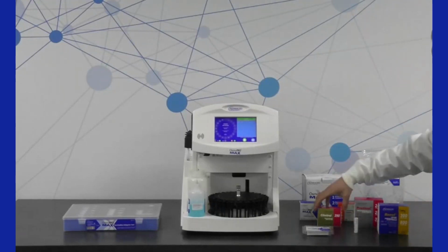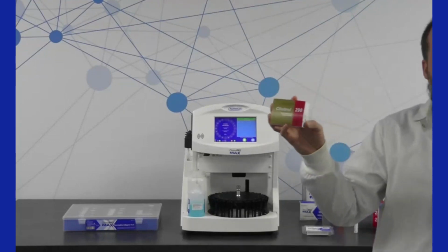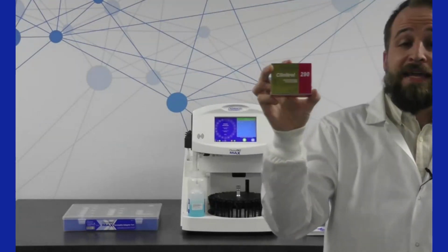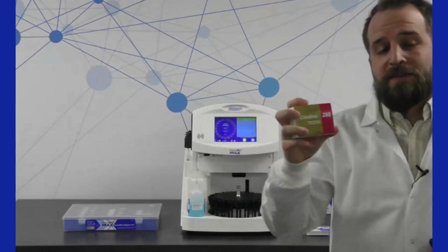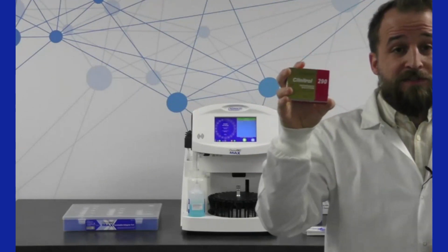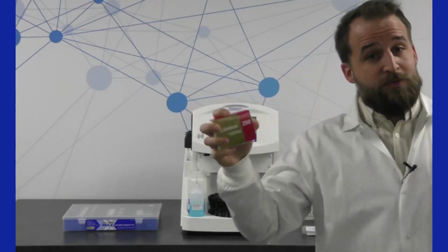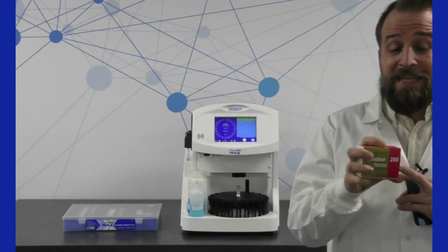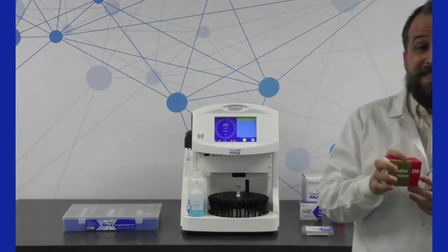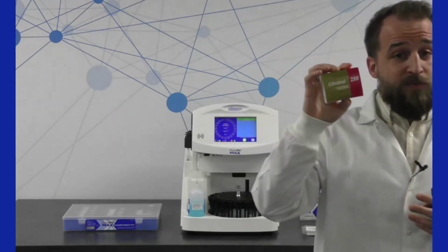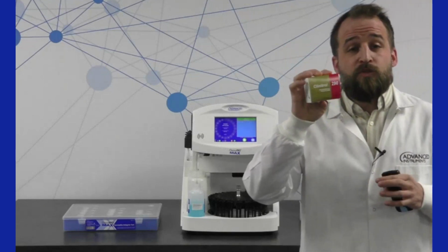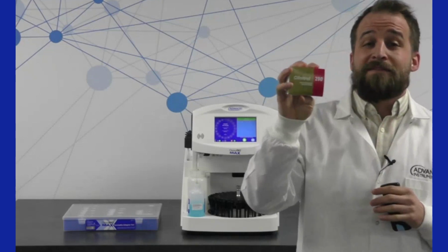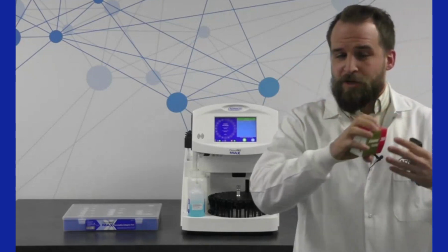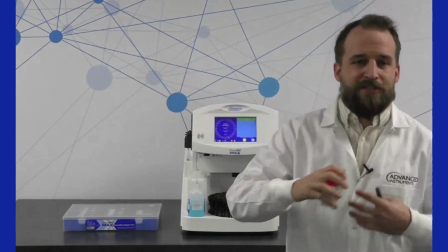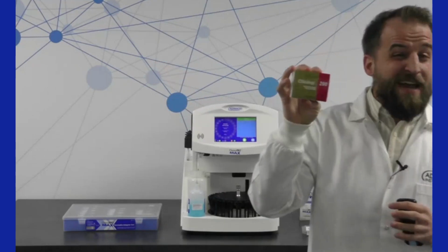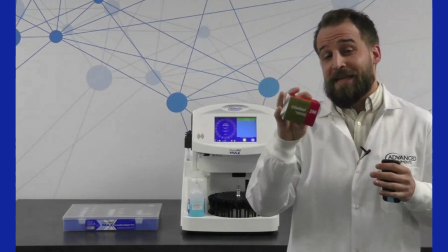As far as controls go, we have Clinitrol 290, which is a control that we require that you run every 24 hours at a designated time. And I'll get into how exactly you do that on the software. But this is a check of your calibration. So it's a calibration verification, a verification of instrument performance. And it also checks to see if something that we implemented in the software called a single point adjustment is needed. So if this 290 is run, and it's within plus or minus 2 milliosmoles of the 290 value established at the time of calibration, then your QC passes, everything continues as normal, and you can just test without any interruption.